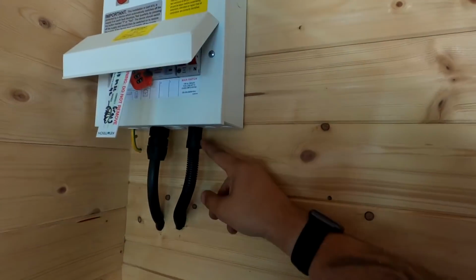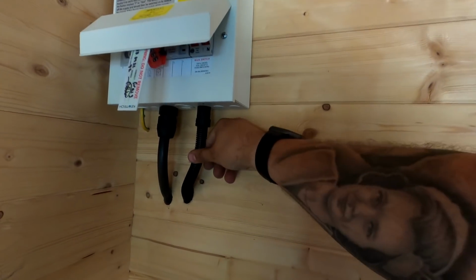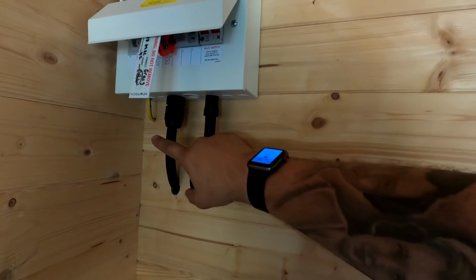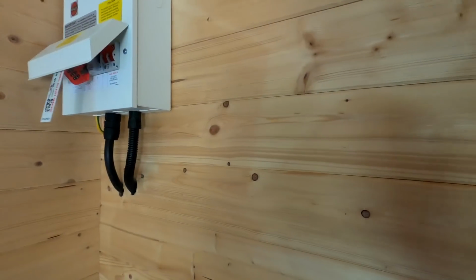We've got our new supply coming in, and our TT rod down there - we're getting just over 13 ohms, which I think on a TT system is blinding. That's our main incoming, and that's our outgoing to the next board.